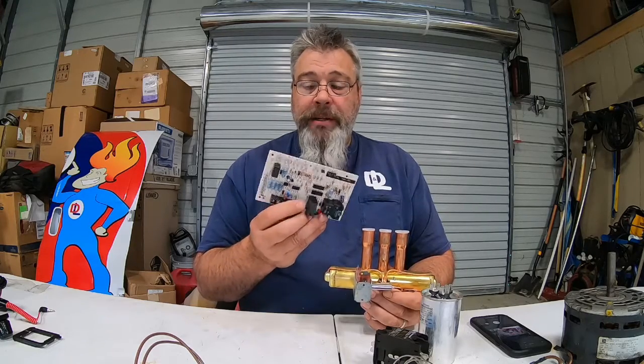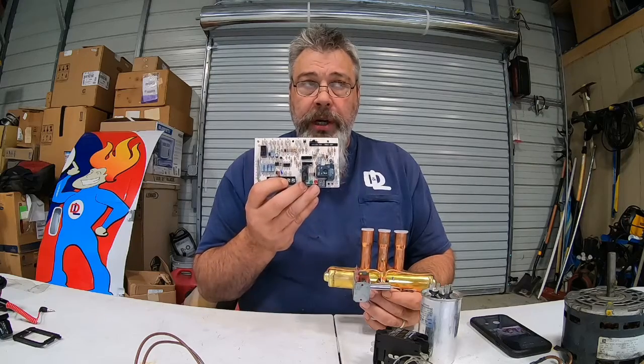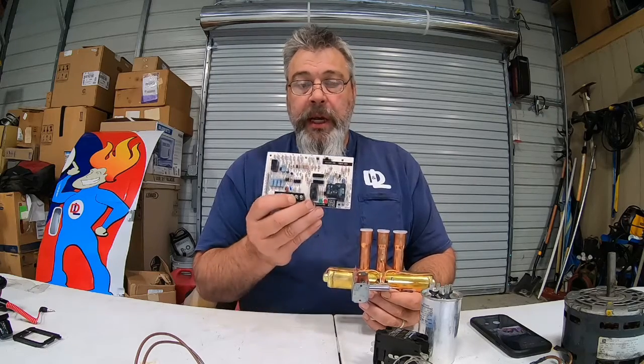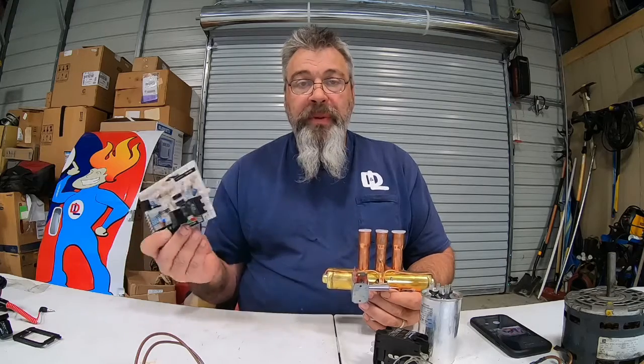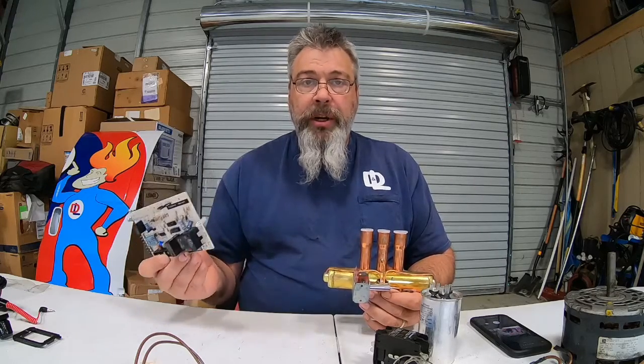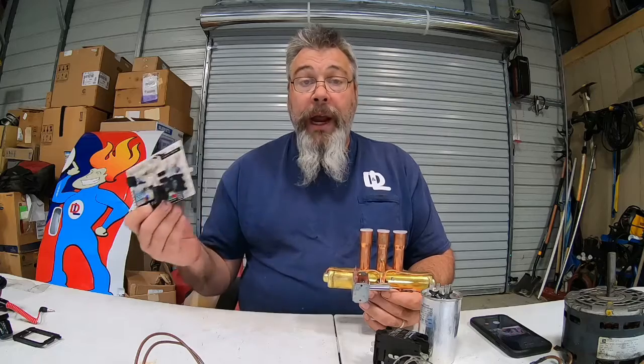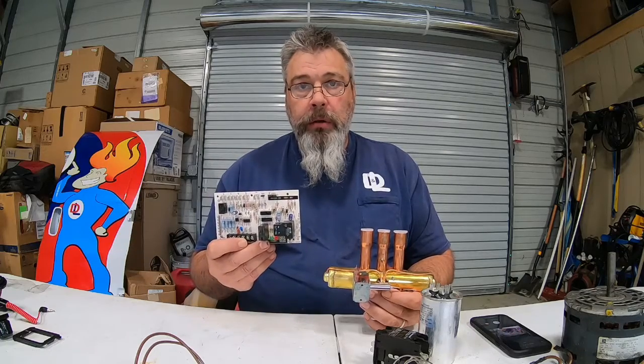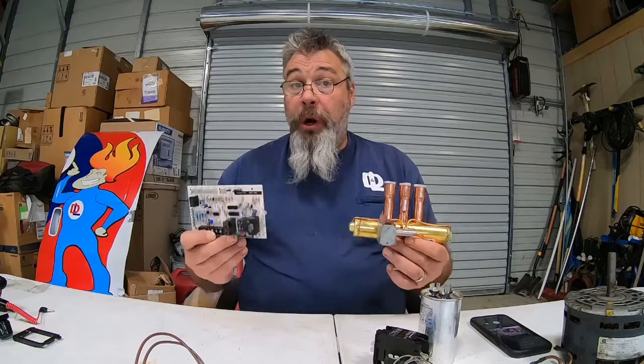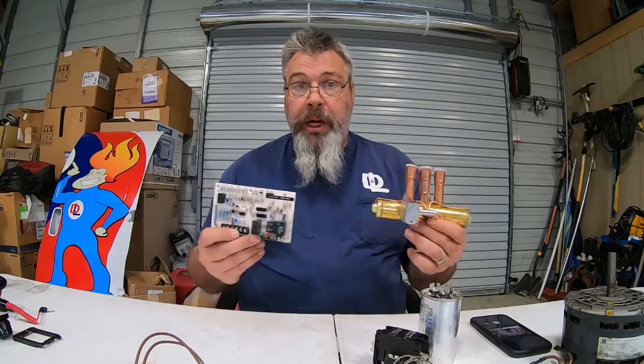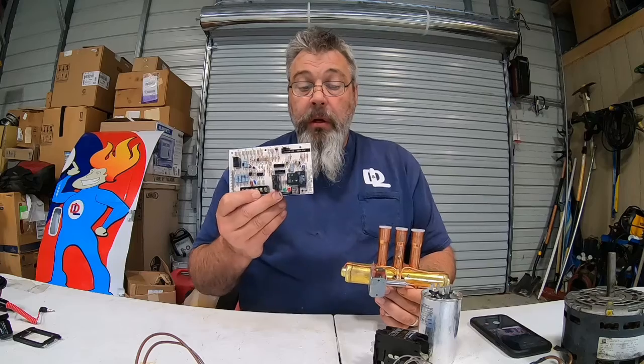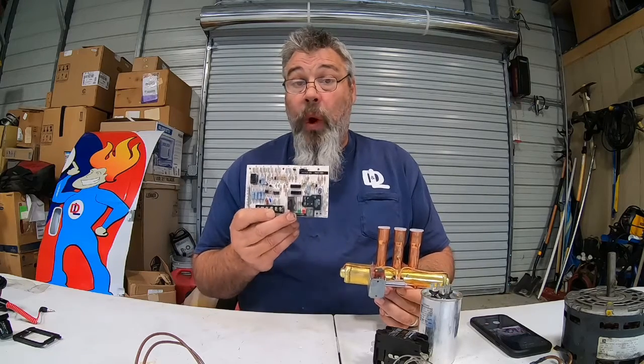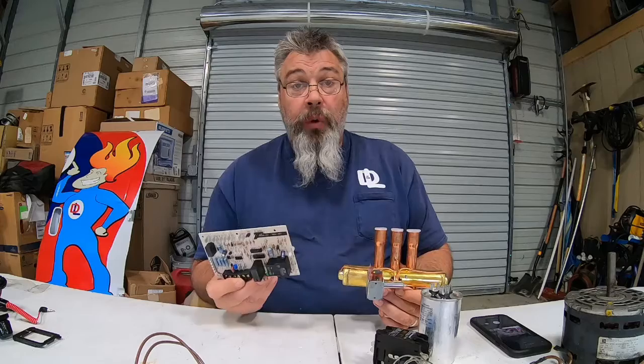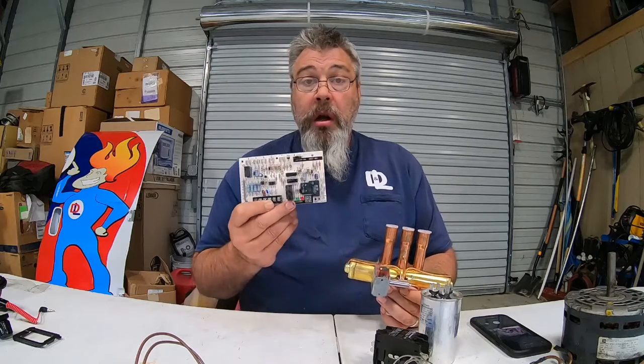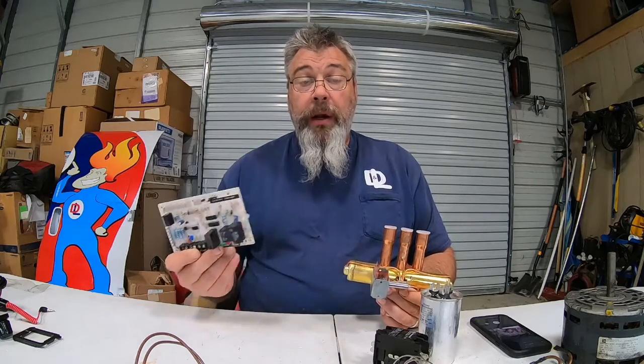And that electric strip heat is initiated through defrost. It sends power back to the air handler, which energizes the contactor or sequencers on the air handler, which turns your electric strip heat on. So there's a lot of things going on when defrost is happening. There's a lot of things to look at when units are either going into defrost or not going into defrost, and how long they stay in defrost. But then we turn your electric strip heat on, and guess what? That electric strip heat is raw heat.